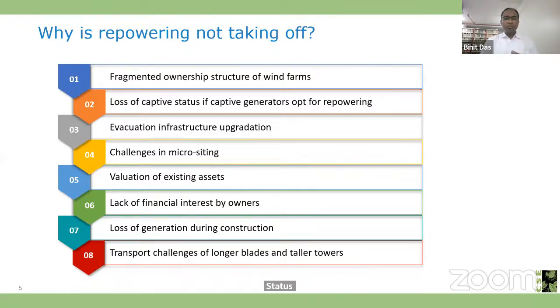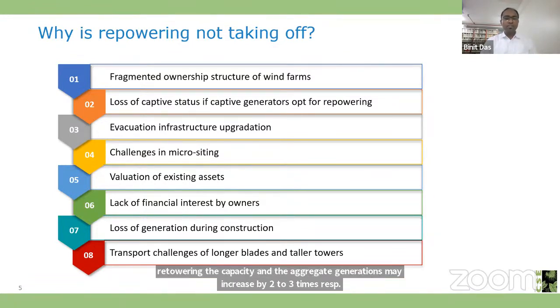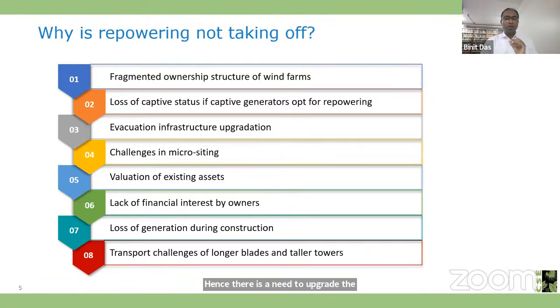Next, in Tamil Nadu, most wind farms are connected to 11 kV lines for power evacuation. However, post-repowering, the capacity and aggregate generation may increase by 2 to 3 times respectively. Hence, there is a need to upgrade the existing infrastructure so that all the energy generated can be evacuated properly without congestion. So there are infrastructural challenges as well.